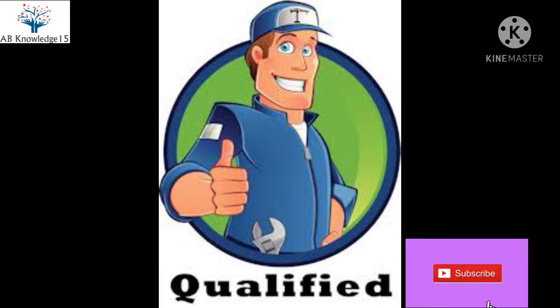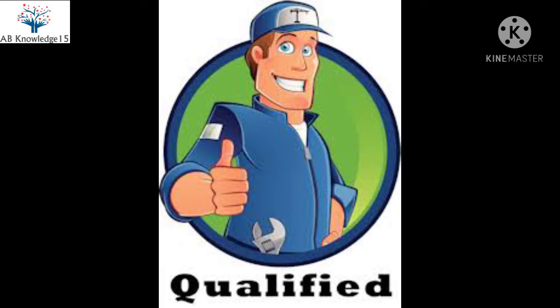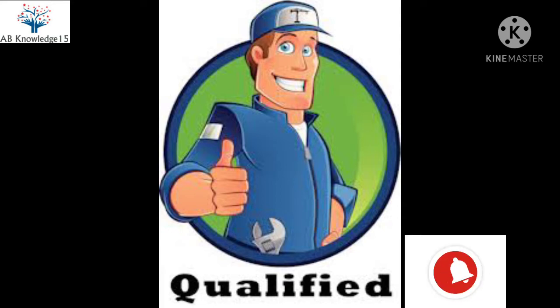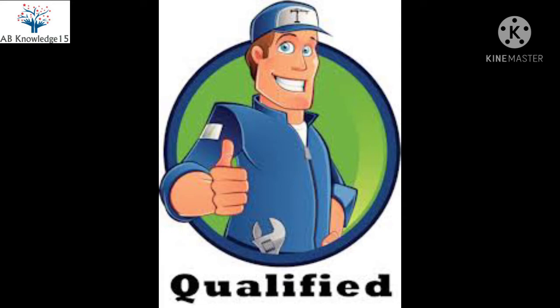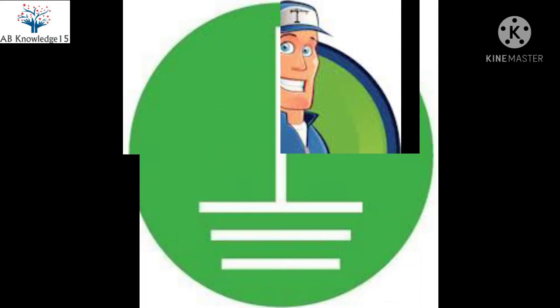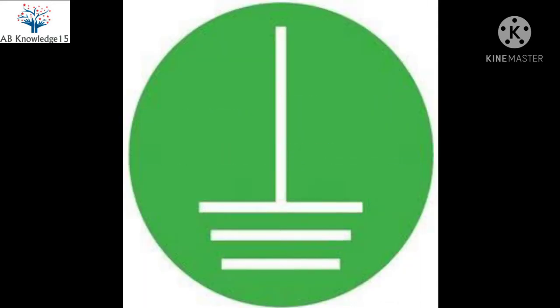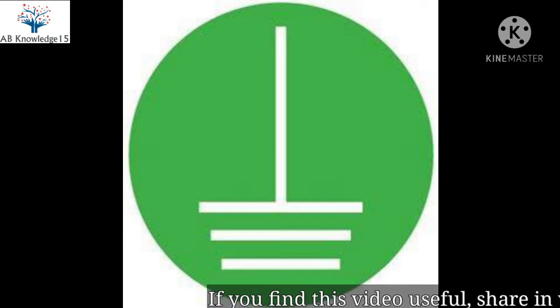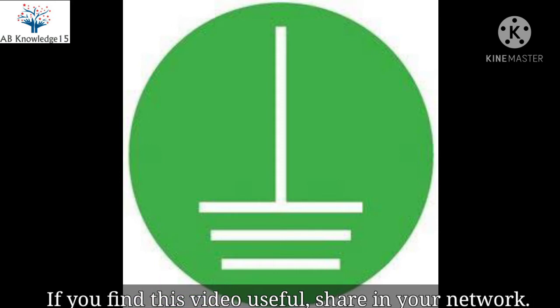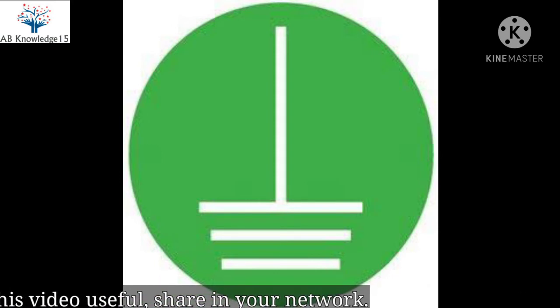The presence of an experienced and qualified person should be there to properly conduct the test and remove any errors during the test. Verify the transformer earthing condition, because the transformer resistance measurement kit several times discharges the transformer into the earth connection.